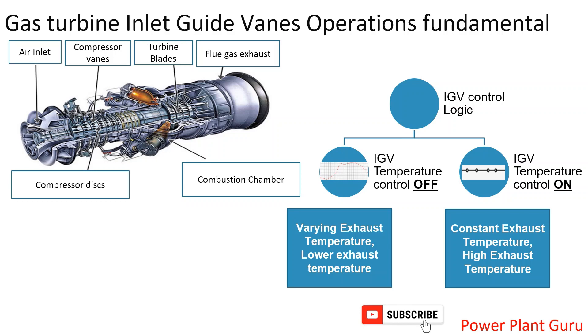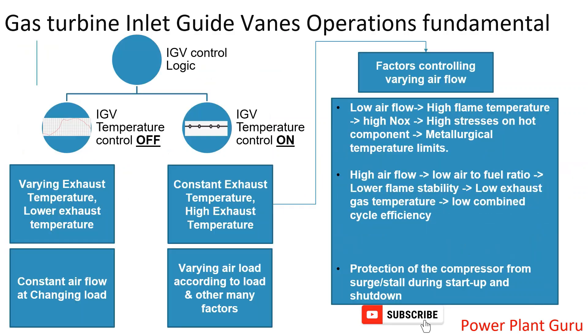Going deeper into IGV operation — how are the boundaries decided? The lower temperature boundary, which corresponds to higher air flow: if you increase air flow, the air-to-fuel ratio increases. Per unit quantity of fuel, more air is flowing, so flame strength in the combustion zone becomes low and approaches the lower stabilization limit. That is the lowest temperature limit, meaning the highest air flow, and this leads to lower combined cycle efficiency.